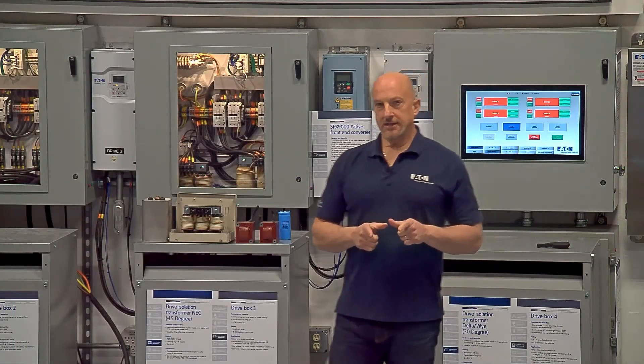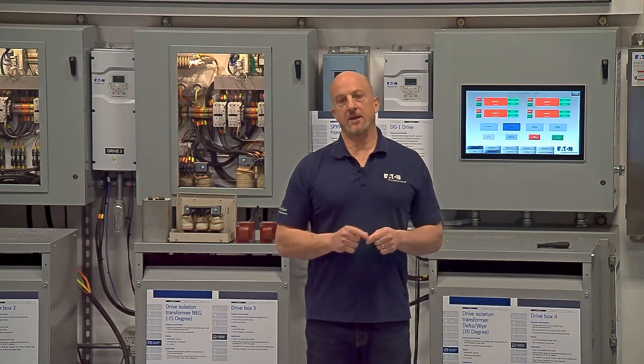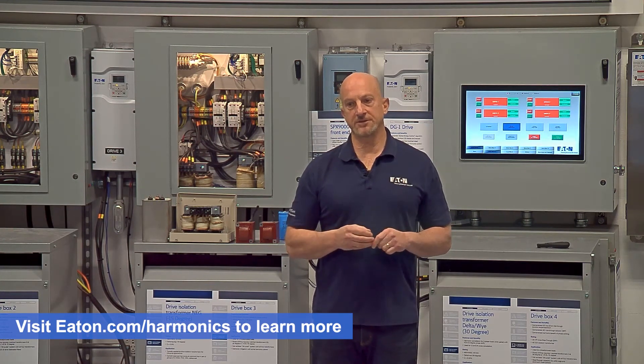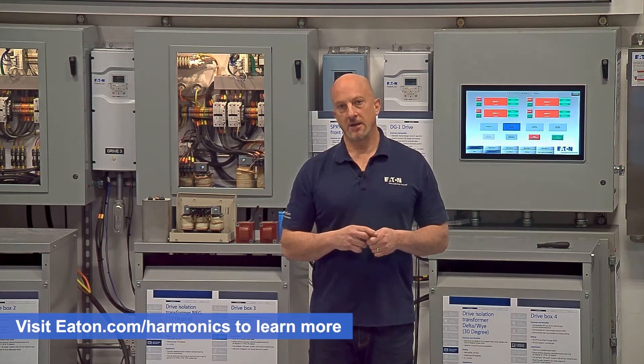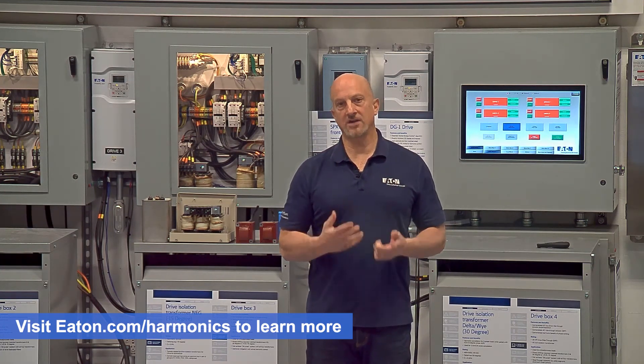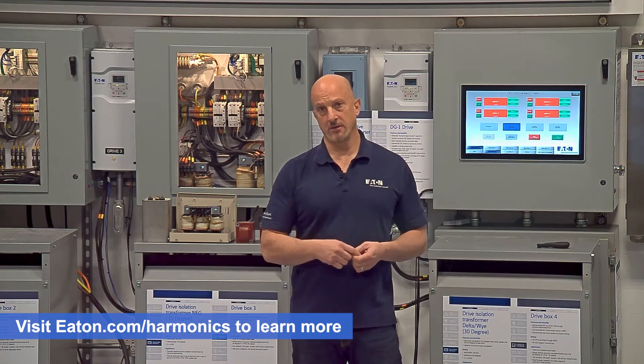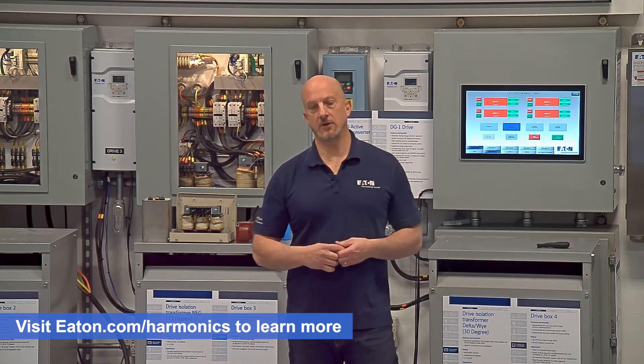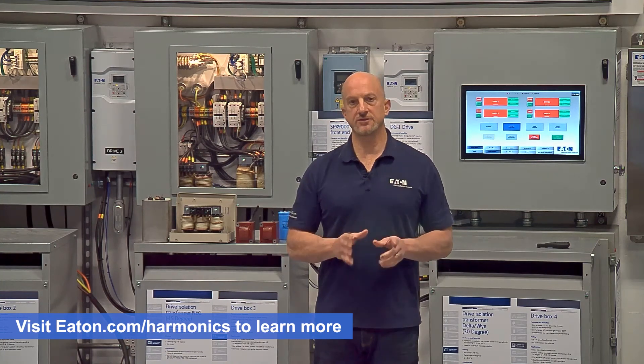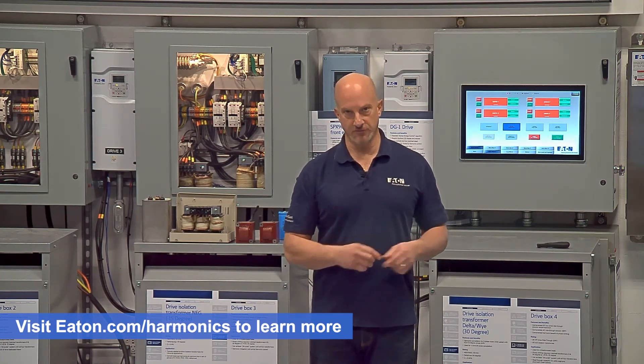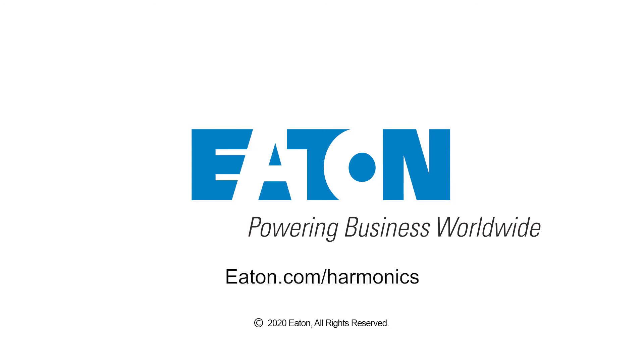So again, as you look at that and you think about what that means for us, just because my percent distortion is high, it doesn't mean that my overall actual amps of harmonic is higher overnight or during these off-load times. So again, it's just one of the questions we get a lot of times. Just be very clear on percent distortion versus actual amps. So again, I'll see you next time.